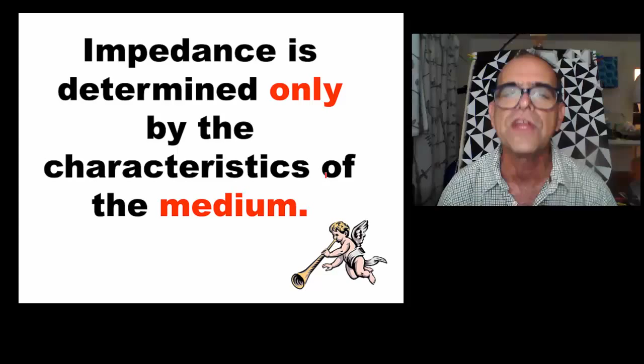Impedance is determined only by the characteristic of the medium. You cannot change the impedance. The impedance is in the body, like the propagation speed. It's a characteristic of the body. You cannot change the impedance of any structure because these things are in the body. Impedance is not operator adjustable. Impedance is only determined by the characteristic of the medium, in this case, soft tissue, because we scan soft tissue.